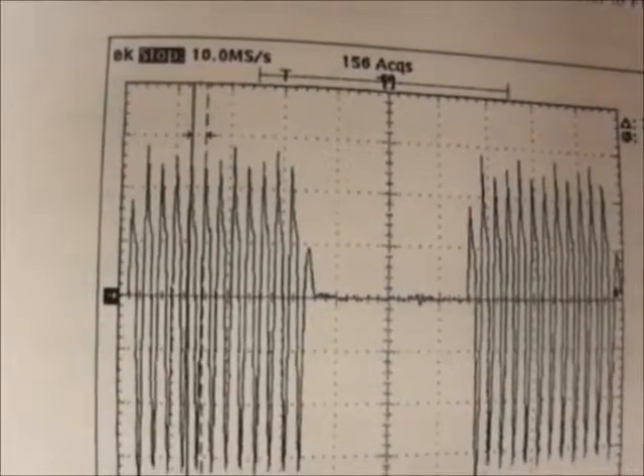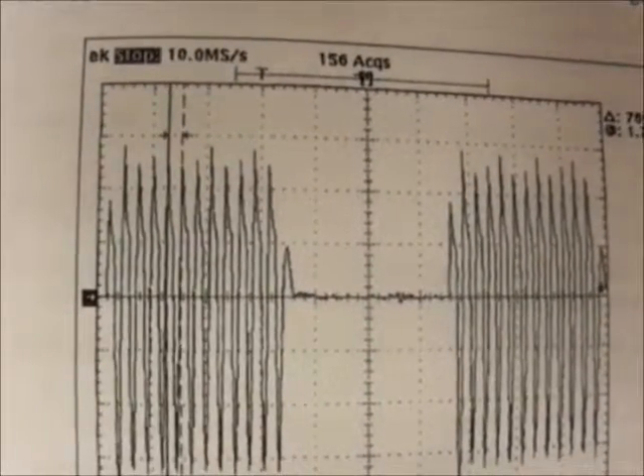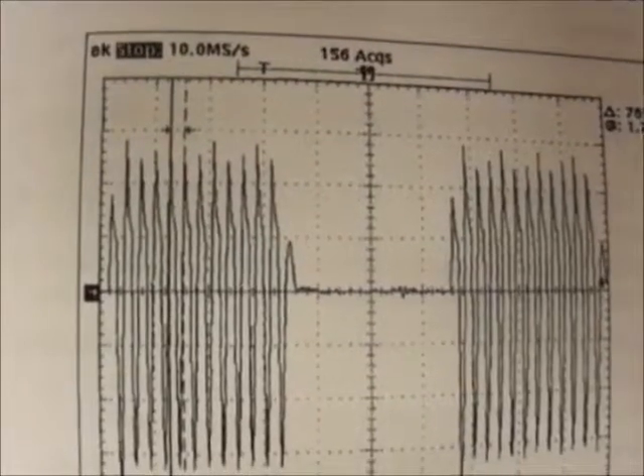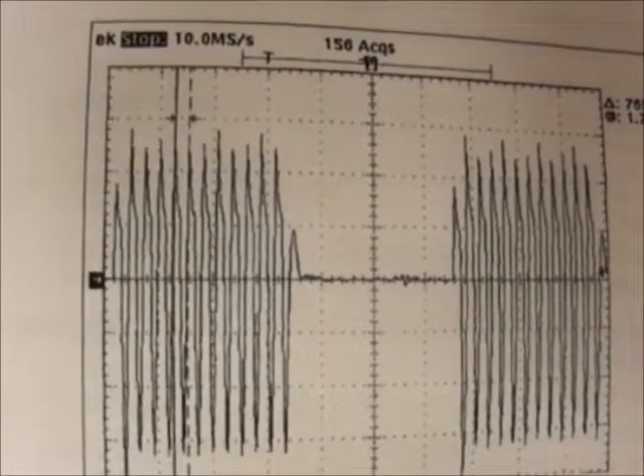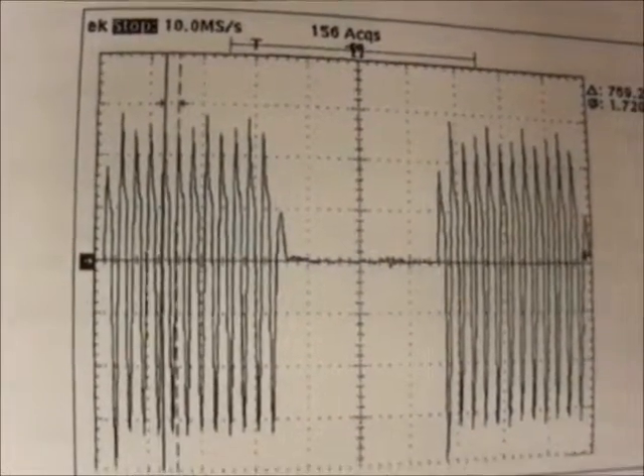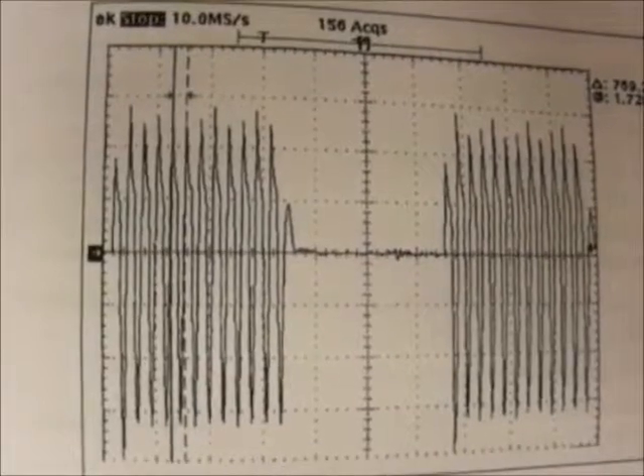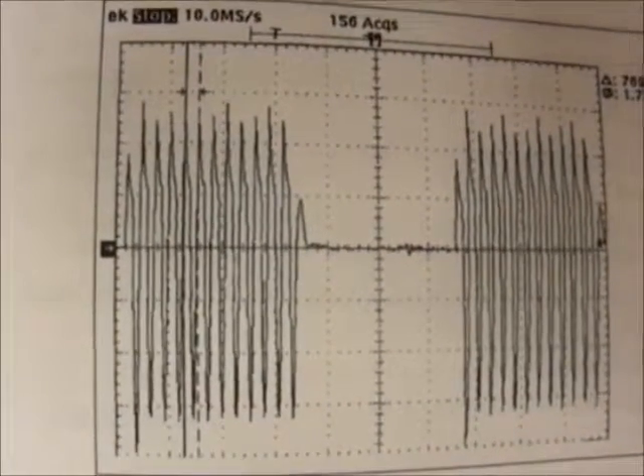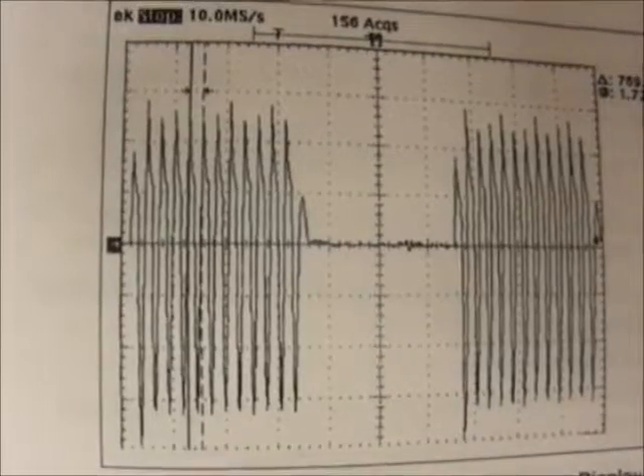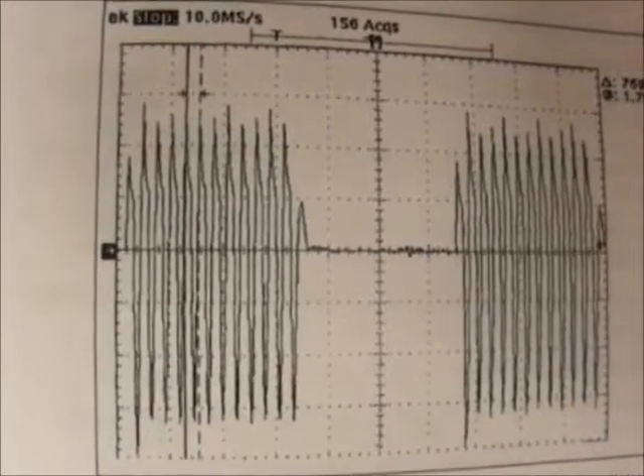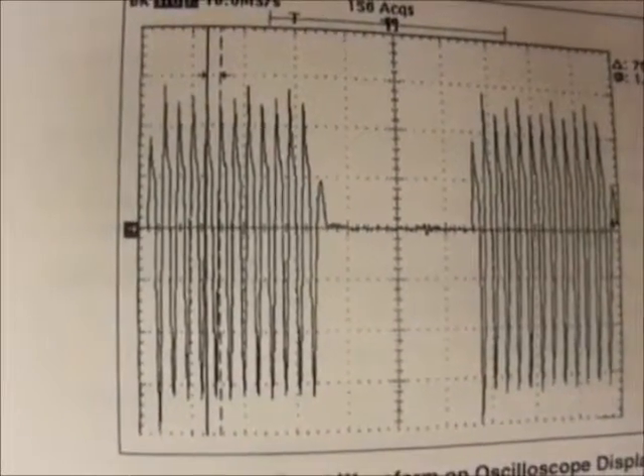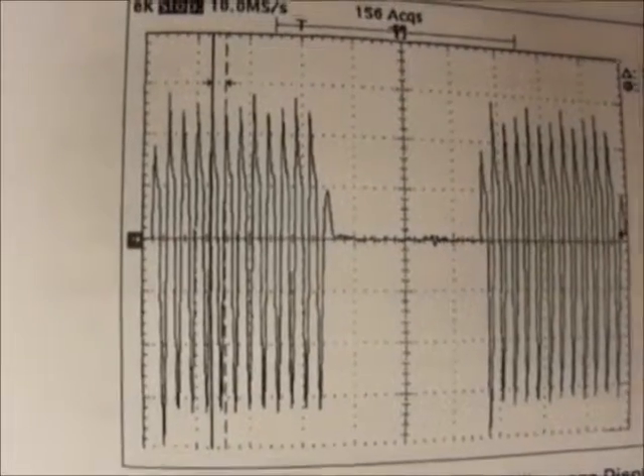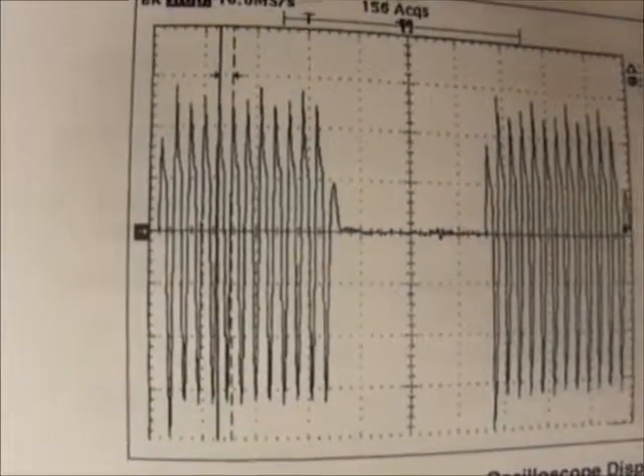Why do we measure Crest Factor? As a means of testing incoming power quality, random noise, harmonic distortions, brownouts, etc., of the input or output voltages or input-output current signals. Good power coming in should equal good power going out.